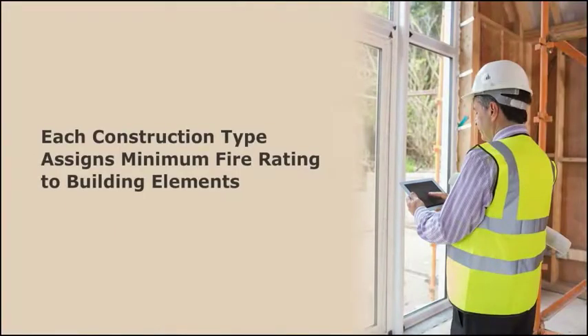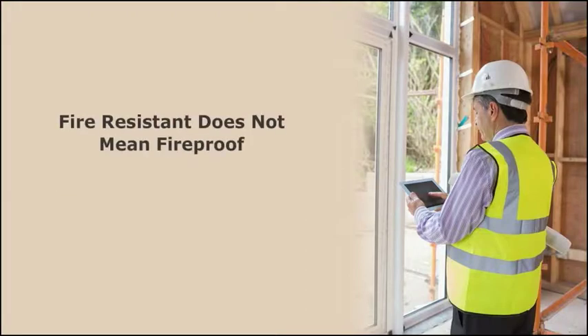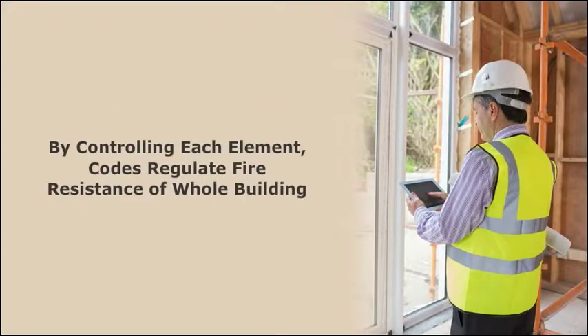Each construction type also assigns a minimum fire rating to building elements. These ratings are based on the number of hours the building element must be fire resistant, meaning that it will not be adversely affected by flame, heat, or hot gases. Note, though, that fire resistance does not mean fireproof. Instead, it is an hourly fire endurance rating. By controlling each element, the codes are able to regulate the fire resistance of a whole building.